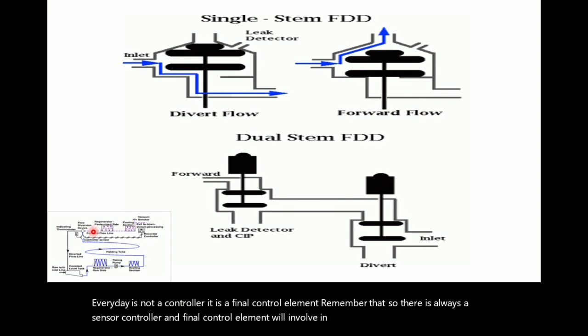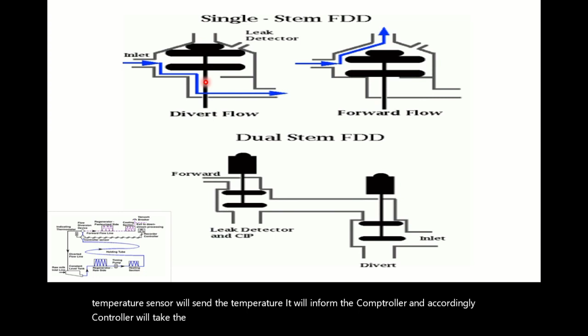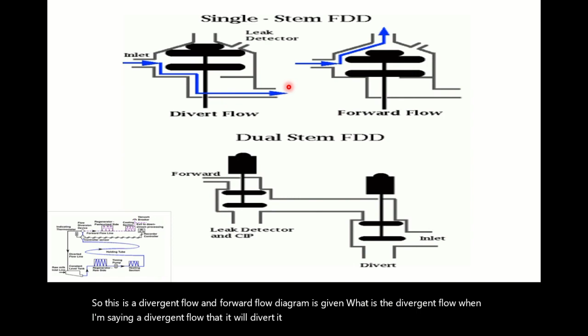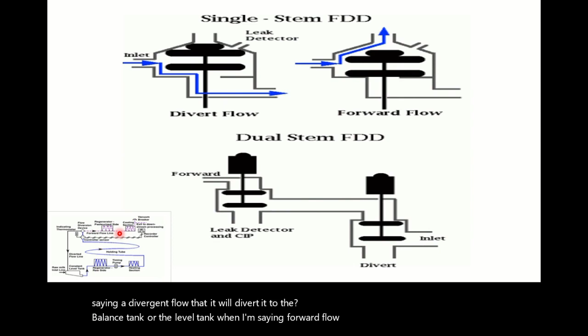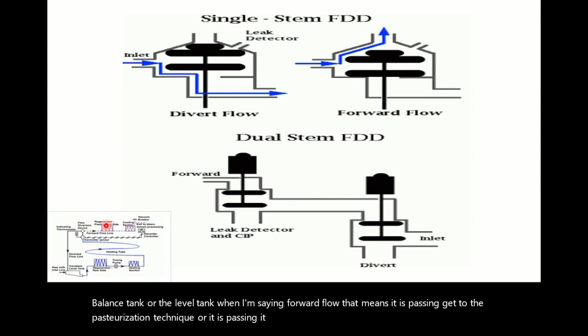So who is sensing it? A temperature sensor will sense the temperature, it will inform the controller, and accordingly the controller will take action to turn on or off, or to move up and down the stem of the control valve. So a divert flow and a forward flow are given. What is a divert flow? A divert flow means it will divert to the balance tank or the level tank. A forward flow means it is passing to the pasteurization technique, or to the further heat exchanger.